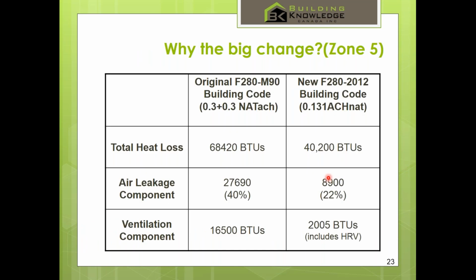If we drag, let's take these numbers down further. Let's take the Zone 5, Toronto, Hamilton area. Of the 68,000 BTUs, 27,000 was the air leakage component based on the old calc, and ventilation was 16. And you'll see that when we apply a 3 ACH as tested with a blower door, all of a sudden we drop threefold down to 8,000. And we put an HRV in at 65% SRE, and all of a sudden we're down to 2,000 versus 16. So you can see one of the reasons for the big principal change.